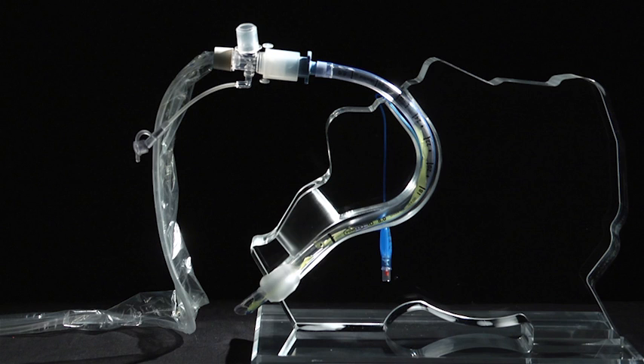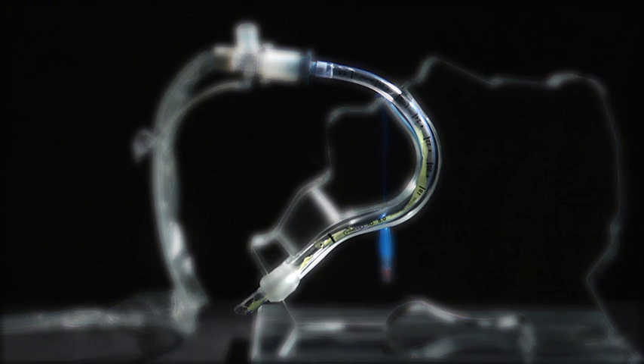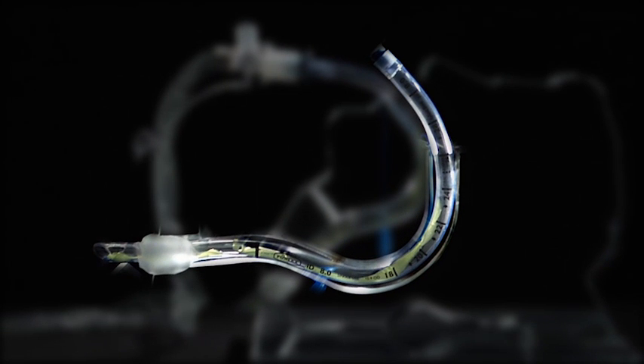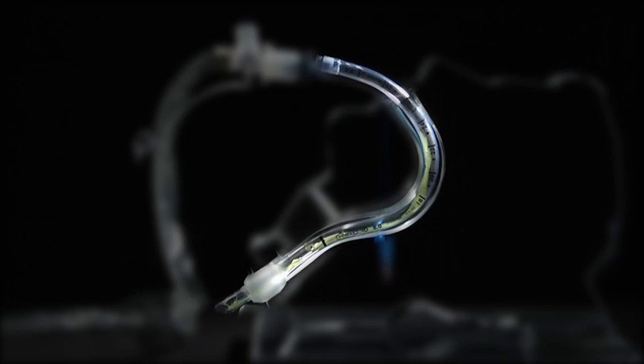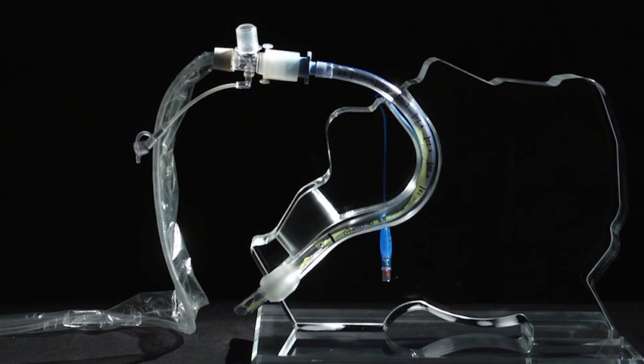Also, the head is inclined at approximately 30 degrees, which is the recommended inclination for closed suction or the endOclear procedure. First, I'm going to make a pass into the endotracheal tube with the closed suction system. The substance inside the endotracheal tube is tenacious and made to mimic the secretions that are in the endotracheal tube in the human, and if anything, these secretions are more easily removed than those in vivo.